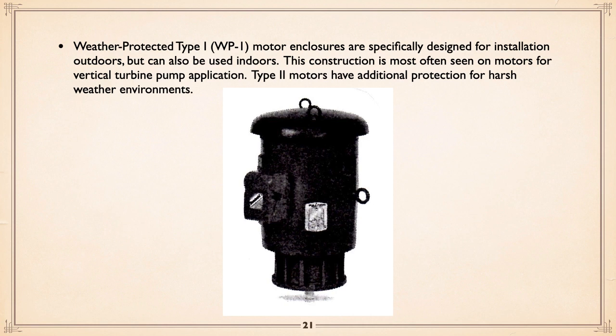They can be used indoors, and very often are, but they are weatherproof. Seen on vertical turbine pumps. The basic, simplest motor enclosure of the vertical turbine pump motor is weather-protected 1. There are also Type 2s, which have additional protection for harsh weather environments, okay?